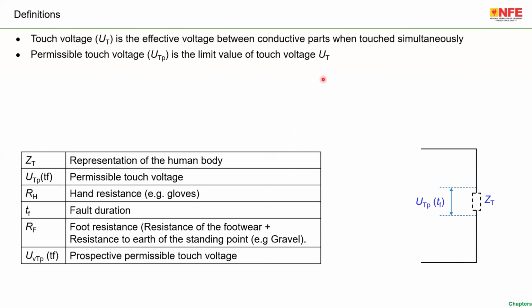Permissible touch voltage is the limit of touch voltage UT. Permissible touch voltage means what maximum touch voltage, what is the limit of the touch voltage over which a person gets ventricular fibrillation, is the question. Now RH and RF represent additional resistance in the body where skilled people are working. For example, you are the technician in the substation, wearing gloves. RH is the hand resistance which represents the gloves, and RF is the foot resistance which represents the resistance of the shoes plus maybe the resistance of the gravel.